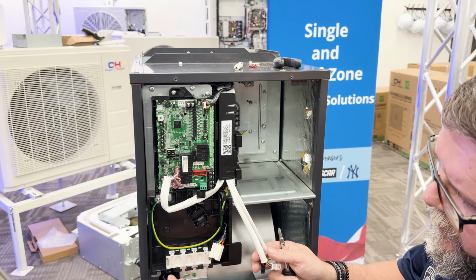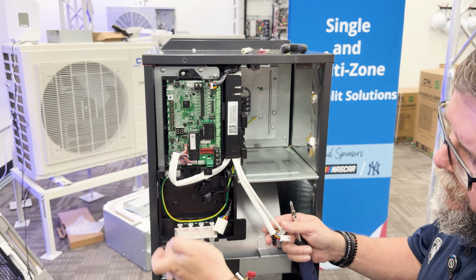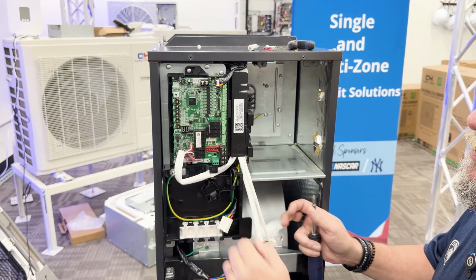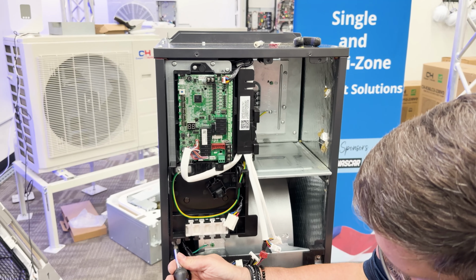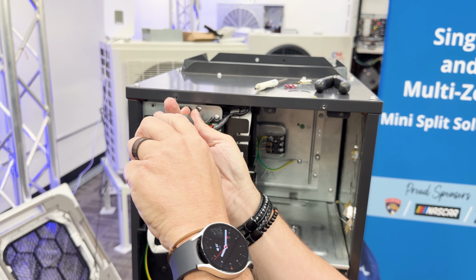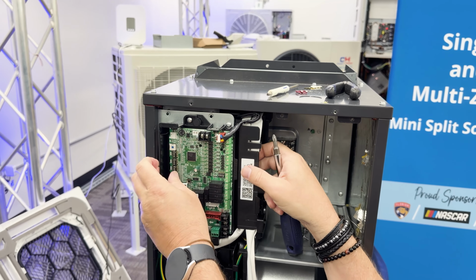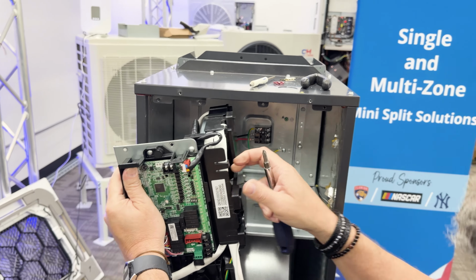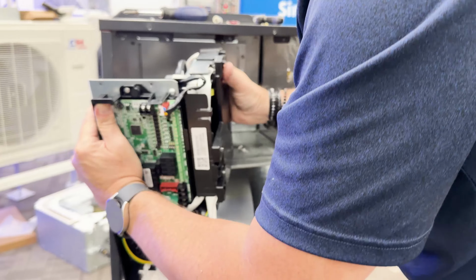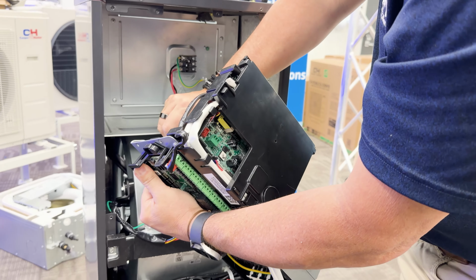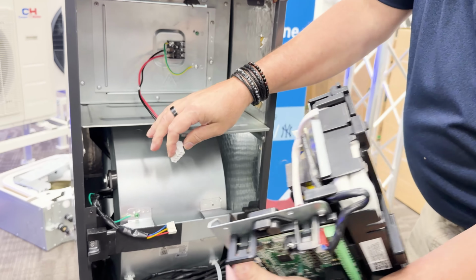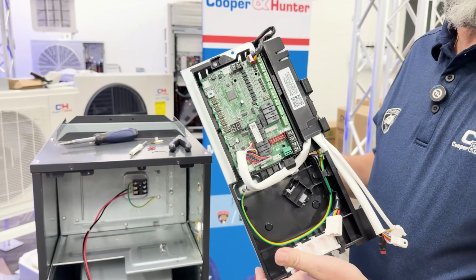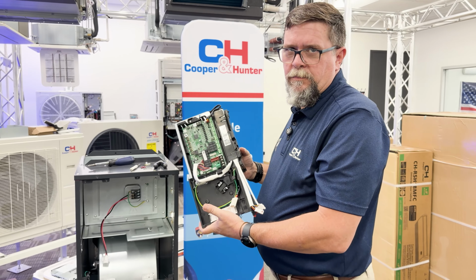With the connectors disconnected, next step is to remove the 3 screws. You've got one at the bottom here, 2 at the top. And with the screws removed, now we should slowly pull out the board assembly. And as you feel some tension on the back side, here is a connector. Pull that connector off and you have a complete disassembly of the board.